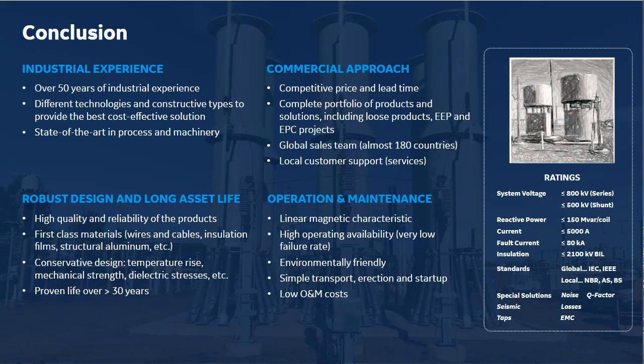Next question, can we specify Q factor, or is it better to let GE decide? So the answer is, it depends. There are some specifications or some applications that have a specific Q factor requirement. For example, filter reactors. The Q factor is related to the filtering aspect of that design. And yes, for these types of applications, we would need to know exactly what Q factor you need, because we can change the design of the reactors for that specific Q factor, and that actually has a considerable impact on it. So for other applications where a Q factor is not mandatory, I would say you don't need to mention or to specify a Q factor.